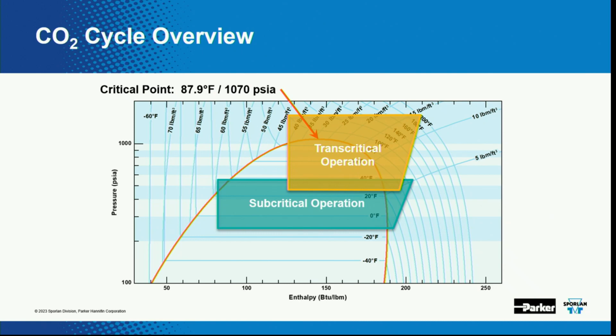So we have to add a whole other trapezoid onto our slide, because what happens is that if the ambient conditions are above 87.9, then we don't have liquid CO2. So we've got a little bit of a problem there. So what we're going to do, and we're going to get into that a little bit more later, but we're going to show you how we can handle the CO2 up there in that transcritical realm.